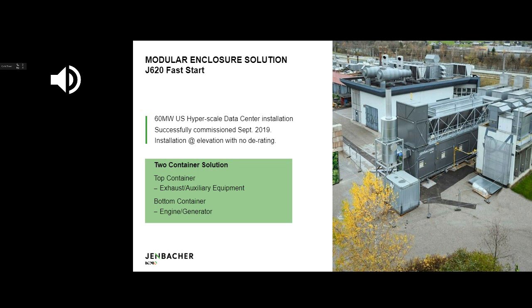The fast start power quality is one of the keys mentioned earlier. It's not necessarily just fast start — we also need a good transient response, which met the customer's requirements. This was achieved through port injection to mimic a diesel application. This is a 60 megawatt hyperscale data center here in the U.S.